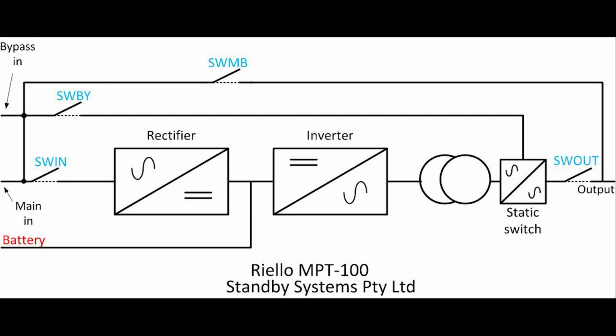The purpose of the static switch is to maintain power on the load should a fault occur on the inverter. In other words, if there's a problem with the inverter, the static switch will automatically fire, thus maintaining integrity on the load. In between the rectifier and the inverter is our battery system, and of course the battery charging system.